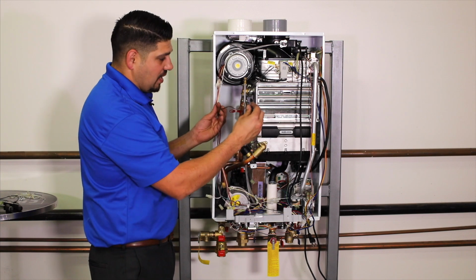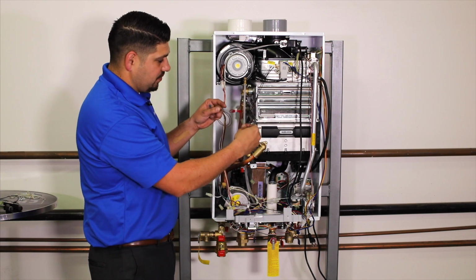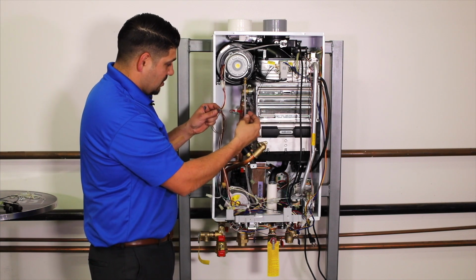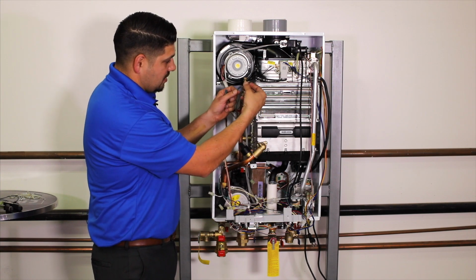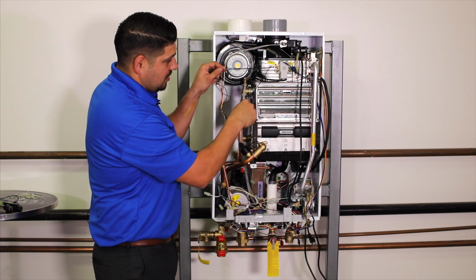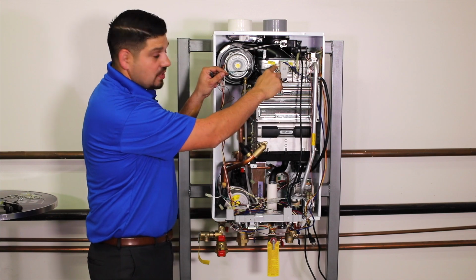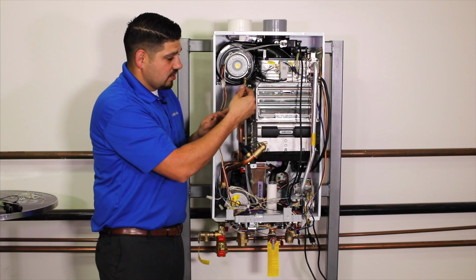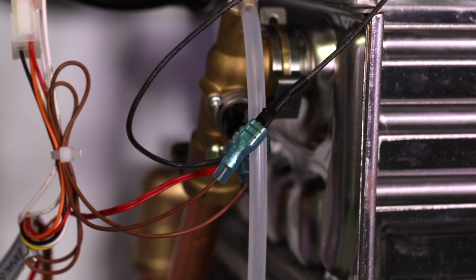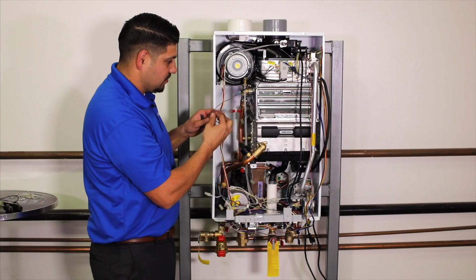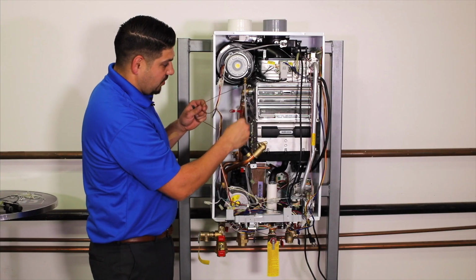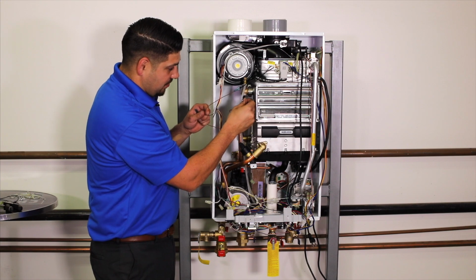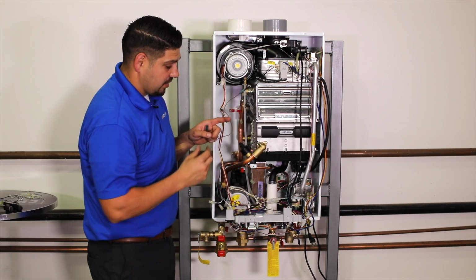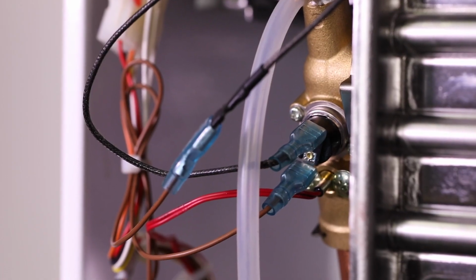Now we have two brown wires. One of them is going to go into our thermal fuse behind your ignition transformer. So the brown wire is going to connect to this black wire, which is a thermal fuse. And then coming out of the thermal fuse, that's going to connect to your high limit on your heat exchanger outlet. And then your other brown wire is going to connect there.